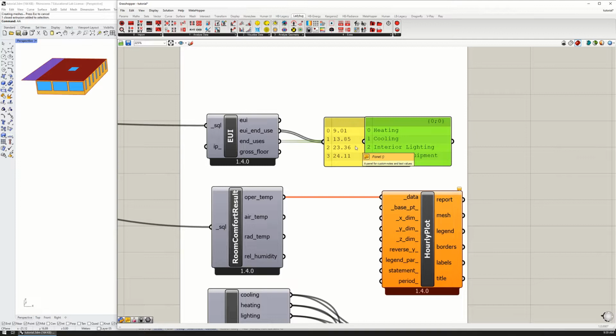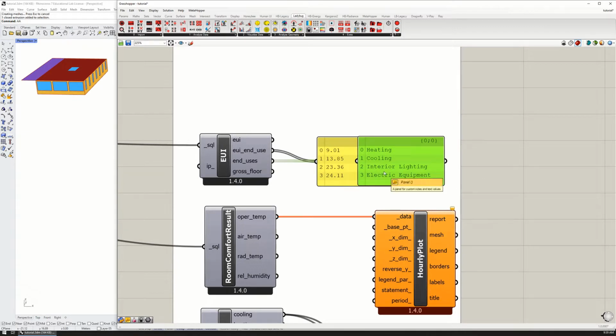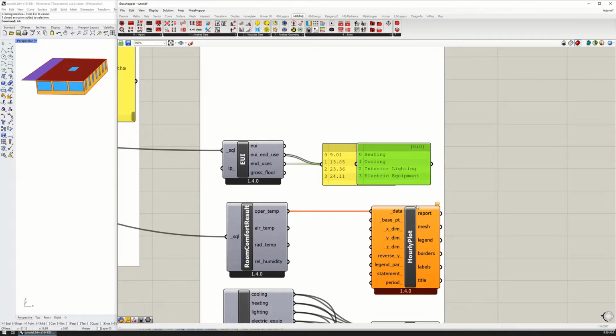So I wanted to take a look at both those thermostat set points and something called the coefficient of performance, or COP. This essentially assumes a COP of 1, or 100% efficiency. And the easiest way to approximate other systems for our case right now, without going into a lot of detail modeling them, or really even understanding all the components of them, like fans and ducts and pipes and heat recovery, heat rejection, all that stuff, is we can approximate these different systems using different COPs, or coefficients of performance. So for example, a very popular heating system, a gas furnace, has a coefficient of performance anywhere between 70% and 94%, depending on the type of system that you have.